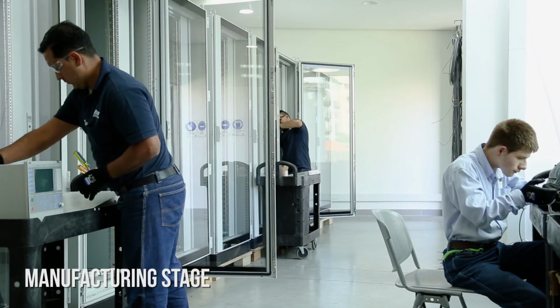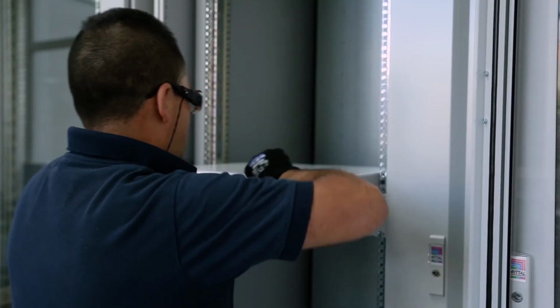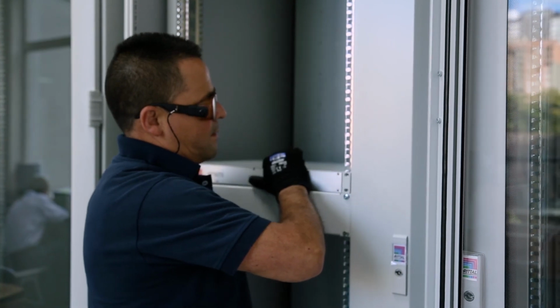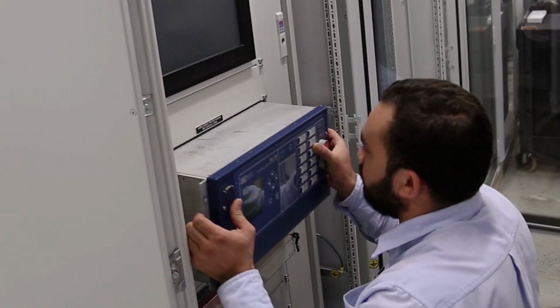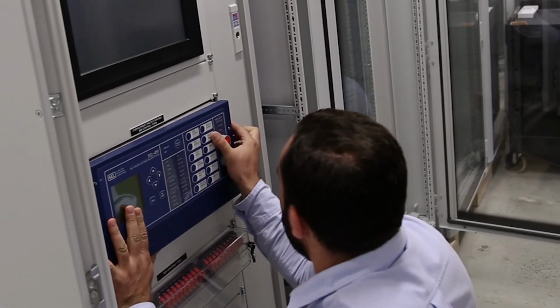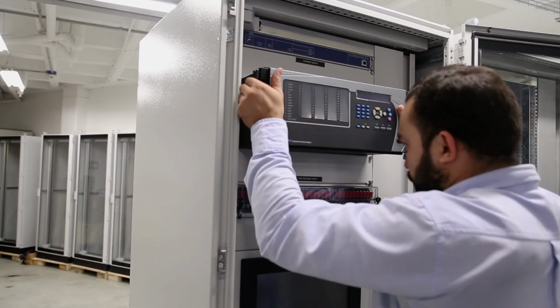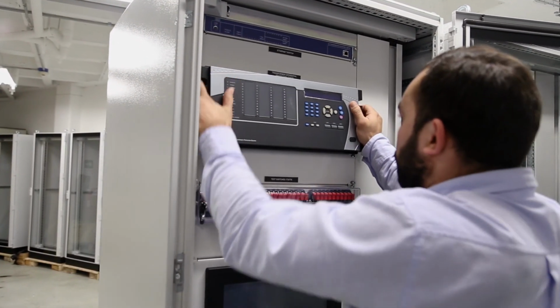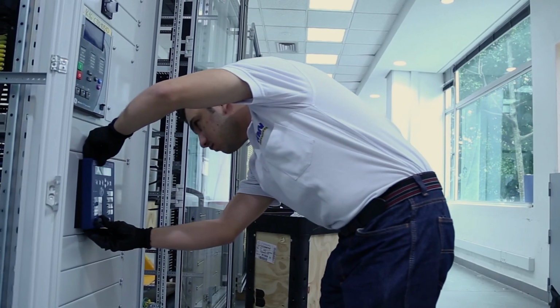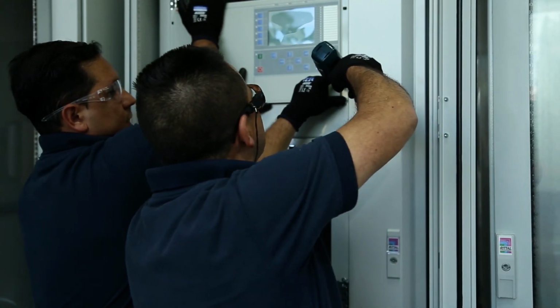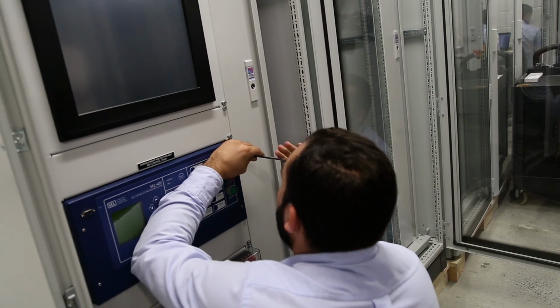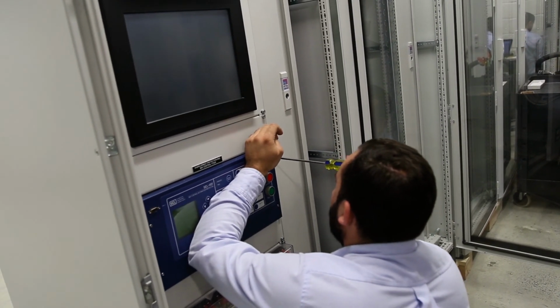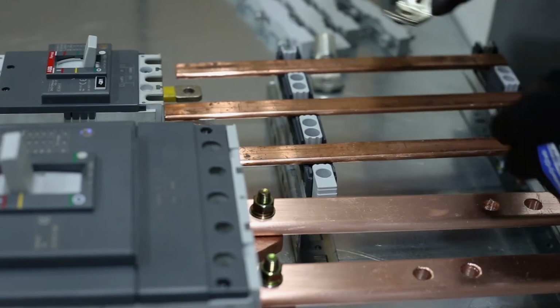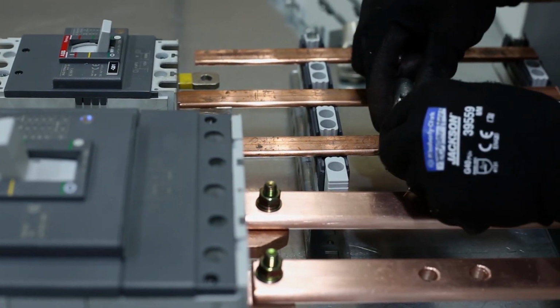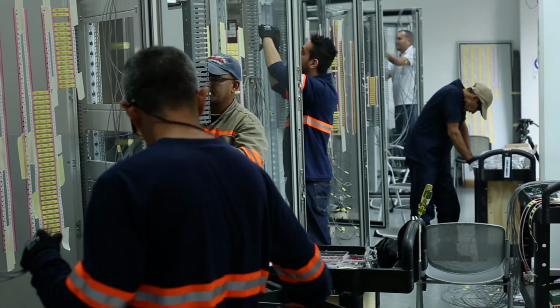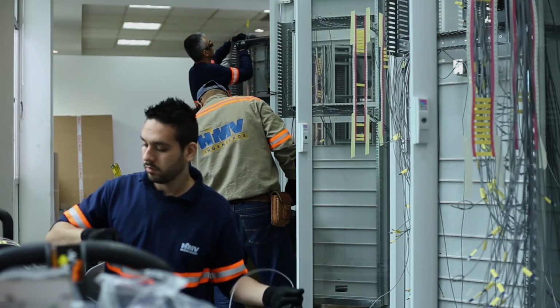At the manufacturing stage, the mechanical assembly of the cubicle is undertaken with the installation of all main and auxiliary devices according to the design supplied by the engineering area. Once the mechanical assembly is completed, the electrical assembly is carried out, including the internal wiring and terminal marking, according to the produced wiring schedules.